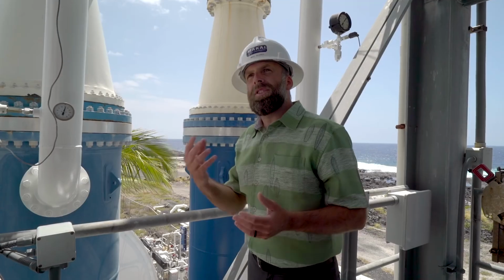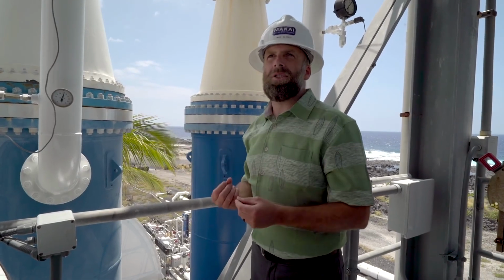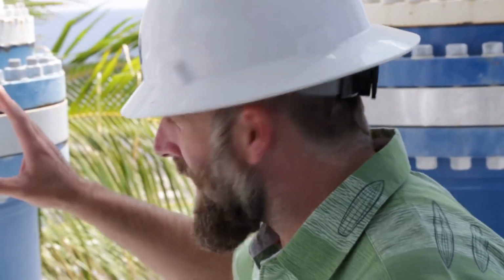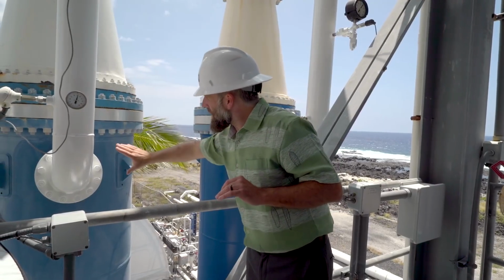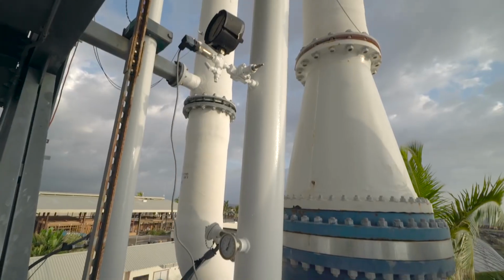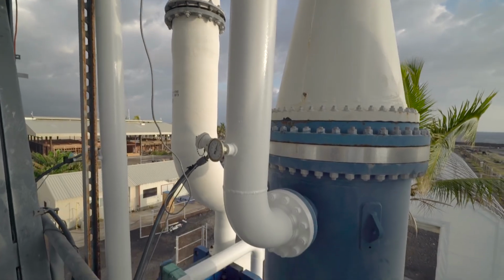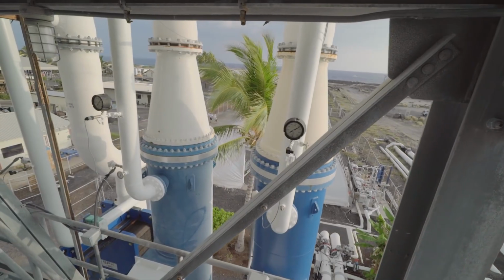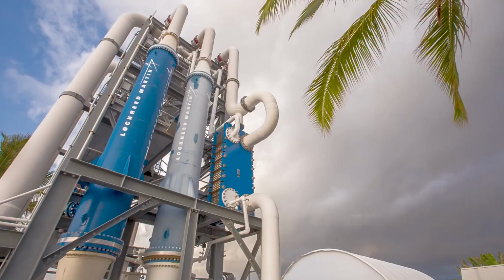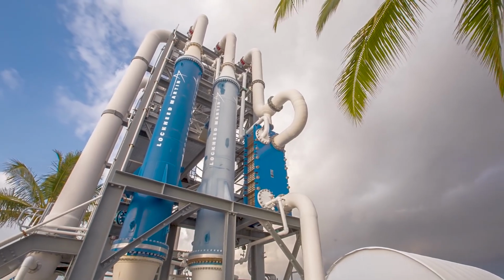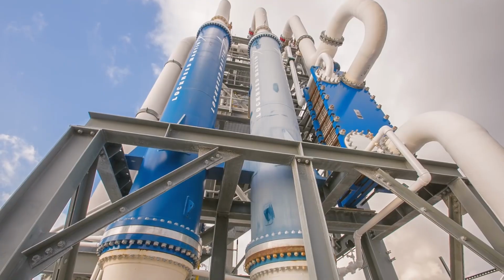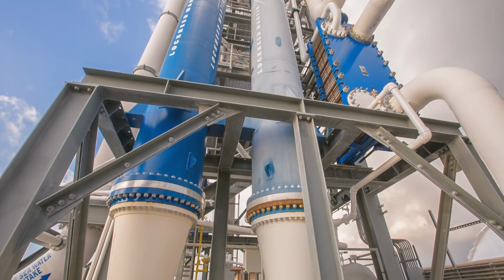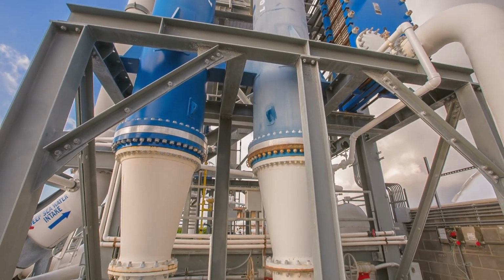After the vapor leaves the turbine, we need to convert it back into a liquid, and so we do that in the condensers. Vapor comes down through this pipe inside this chamber, where there are hundreds of little tubes inside this big tube. The cold seawater passes through these little tubes, and on the outside of them, the ammonia senses the cold, and then it's converted into a liquid and drips down to the bottom where it continues the cycle.